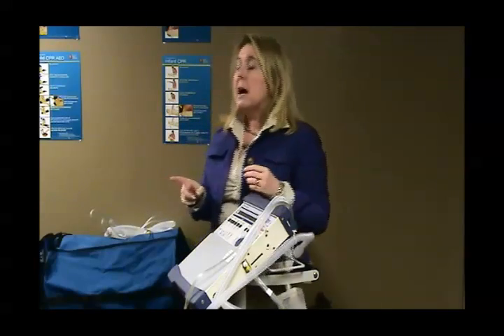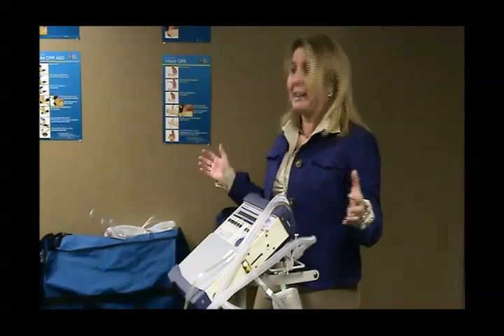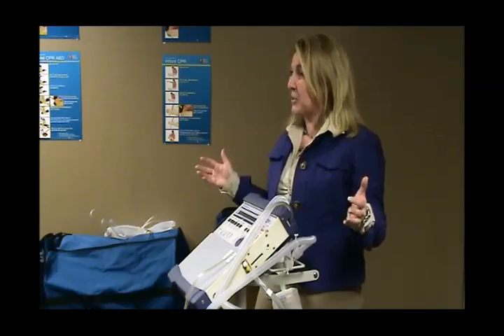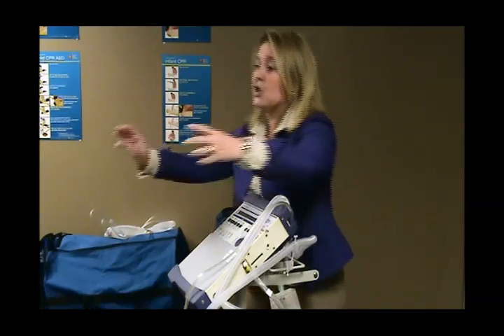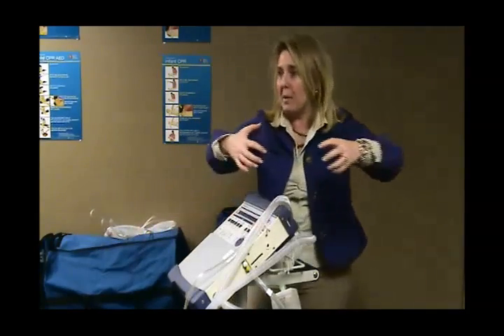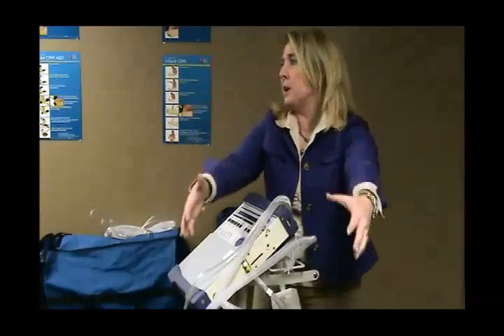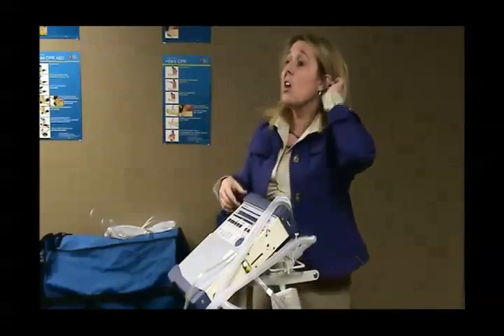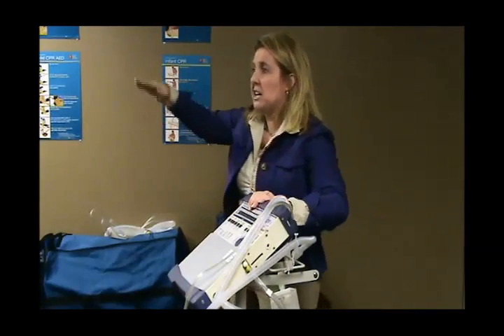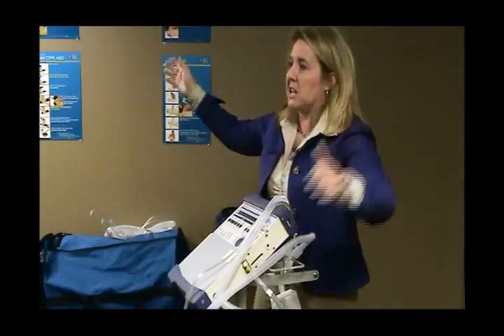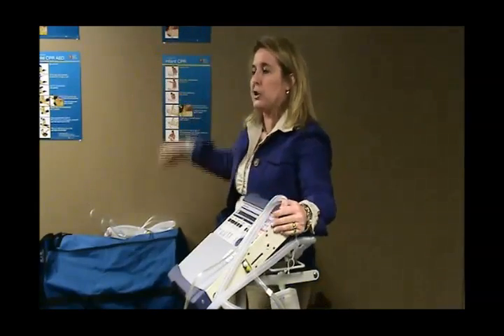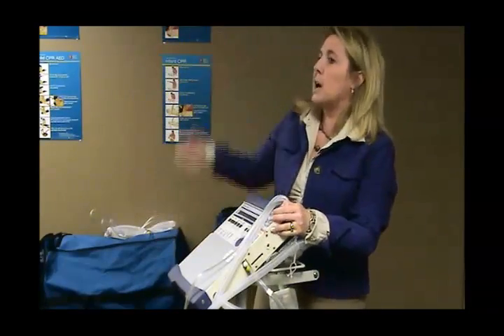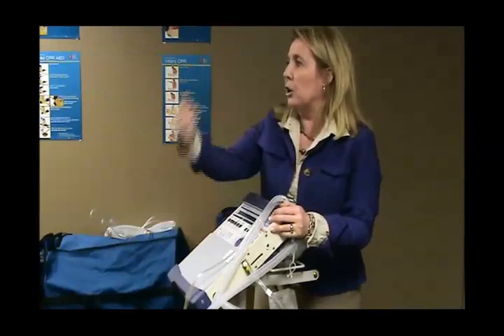Always, always, always. Because sometimes it's blatantly obvious, isn't it? What's wrong with the patient, okay? So start with them, work your way back. So the ventilator alarms high pressure. We're ventilating along, nice normal pressures, let's say in the low 20 centimeters of water pressure, and all of a sudden the pressure shoots up, alarms high pressure. We look at the patient.